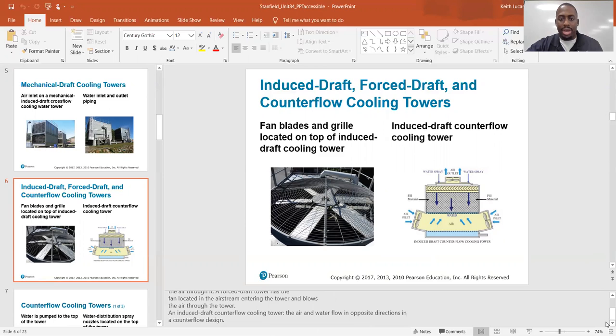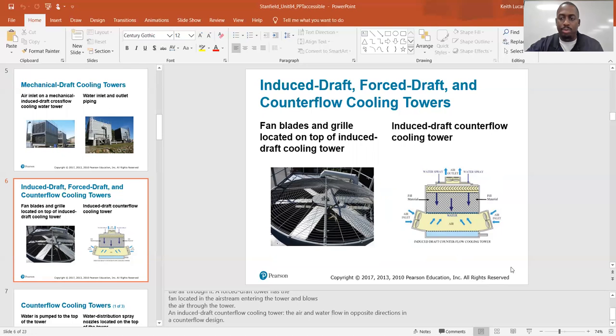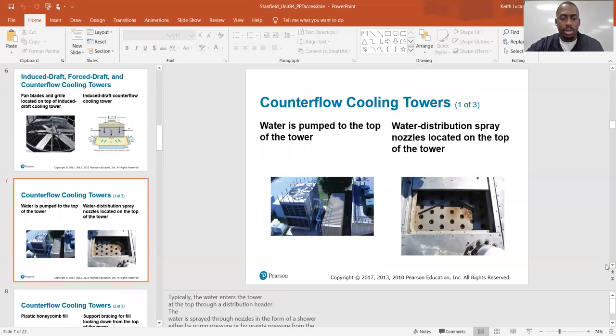An induced draft counterflow cooling tower — the air and water flow in opposite directions in a counterflow design. This would be an induced draft cooling tower, and this would be counterflow. The fan is located at the outlet of the tower, so the air is being drawn in from the sides and blown out through the top — that's induced draft. It's counterflow because the water flow is going the opposite direction of the airflow, so they're going against each other.